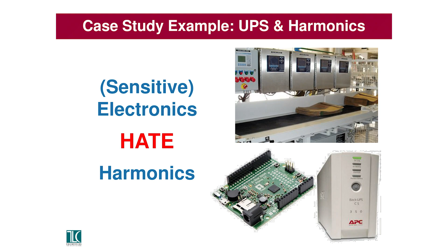We found that these little UPSs that were backing up many, many things throughout this hospital all went crazy. Well, I guess not when it was switching, but when it was on emergency power, those harmonics being produced by those chiller VFDs were just driving it nuts. And it's something we didn't see when they were on normal power, just when they were on emergency power. So it took some time to track down. So it's something to look for.